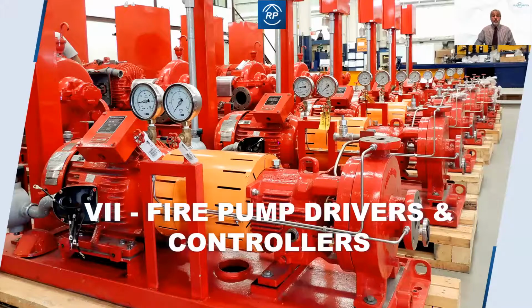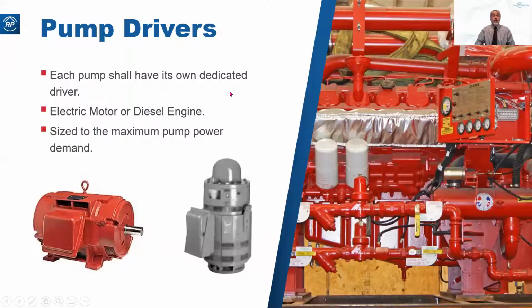So moving on, fire pump drivers and controllers. Every pump shall have its own dedicated driver. Well, big surprise there. Usually electric motor or diesel engine, which should be sized for the maximum pump power demand. And there are sections in NFPA-20 that refer to motors and diesel drivers. And also, of course, there are the UL and FM standards for those items as well.